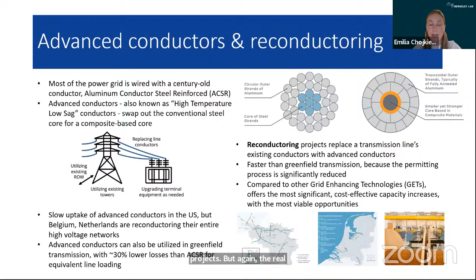I'll note that advanced conductors can also be utilized in greenfield transmission. The key advantage there is that they often carry about 30% lower losses than an equivalent diameter ACSR for the equivalent line loading, so they're also definitely being deployed in greenfield projects. But again, the real benefit is utilizing them in reconductoring projects because of that speed advantage.